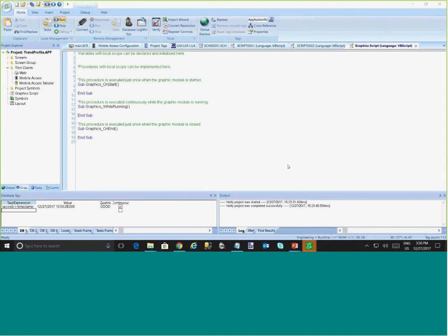It's not a built-in function, but acts more like a ping, waiting for a response from the device on the network, in this case, to get its video. Right, but as long as this ping is executed inside the .NET control, it should not at all freeze the screen while you are waiting for the feedback. And if you are the one creating the .NET control, I would strongly recommend to create an event that lets InduSoft know when the ping finished, so you can treat this feedback accordingly.